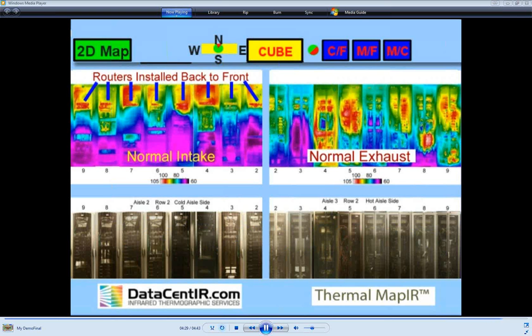The servers in this image are functioning in a normal manner. In each rack, a router has been placed to make wiring easy. This resulted in the routers using the exhaust air from the servers for input, so they are operating at a very high temperature. This one image identified a failure situation that threatened $32 million in equipment.